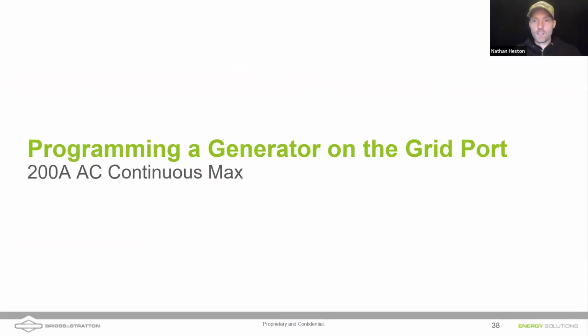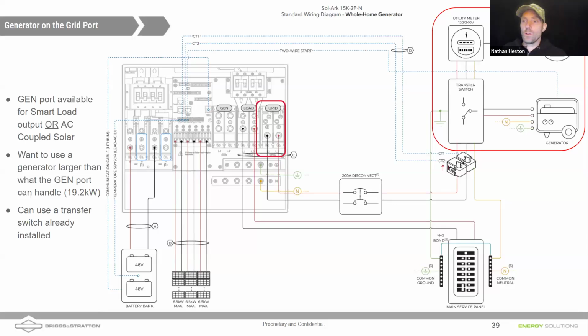All right, so let's go to the grid port. And Daniel, keep an eye on questions in case we've got them, but let's go to putting a generator in on the grid port. So we talked about this earlier. I've shown this screen already. By using a transfer switch, we can now get up to 200 amps of continuous power from a generator. So if you had a larger generator like our 26K Briggs and Stratton, you might want to use a transfer switch so you can access all of that power that you've got from a bigger generator.